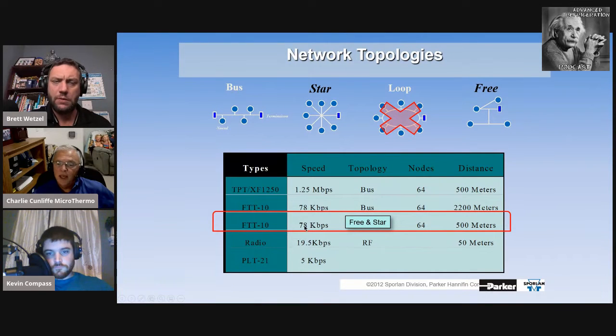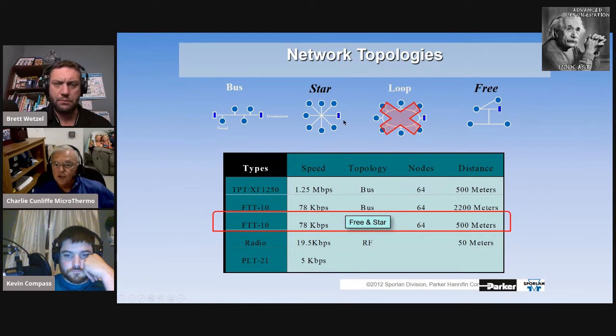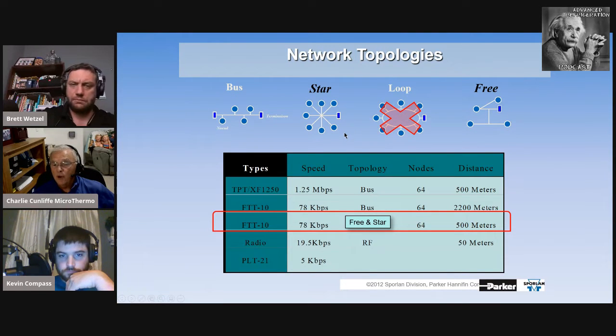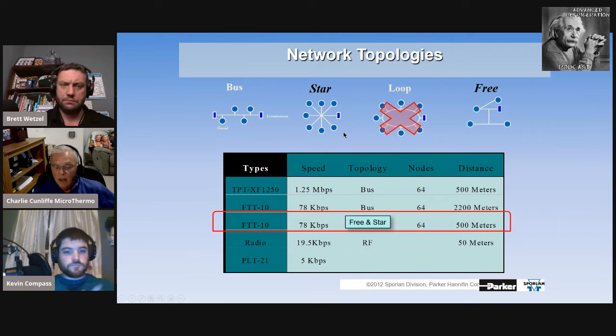The communication we use is FTT-10, at 78 kilobits—78,000 bits per second. The topology we prefer is either star or free, and each network channel can go up to 1,640 feet. We don't want daisy chains—I know that's a term other communication people use, and it's rightfully applied for their technology.